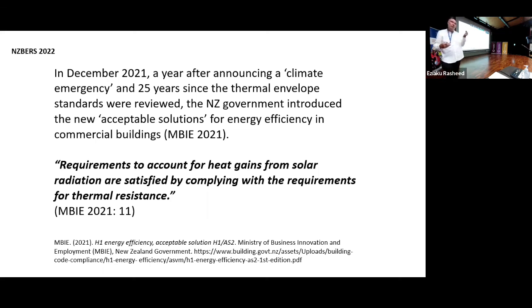There's some partial sense in it, but most of it doesn't make any sense. The partial sense is that the cooling load of a building, if you increase the R values of walls or roofs, has very, very little effect on your cooling load unless you're in an uninsulated industrial shed. But for most commercial buildings, they're already reasonably well insulated. So when the sun hits the walls or the roof, increasing the insulation standards would have very little impact on cooling.